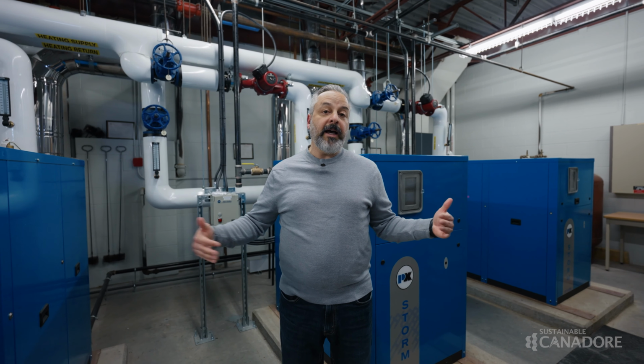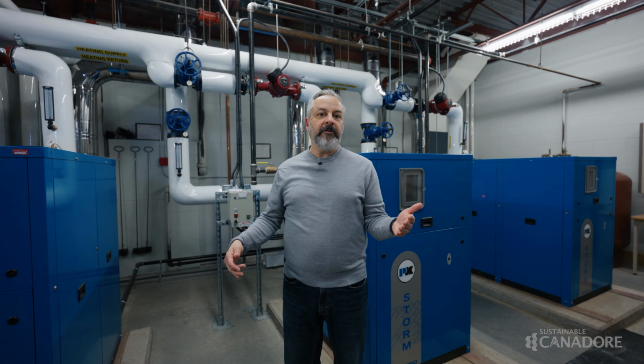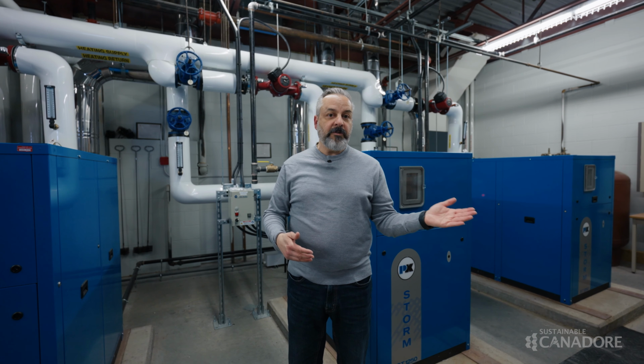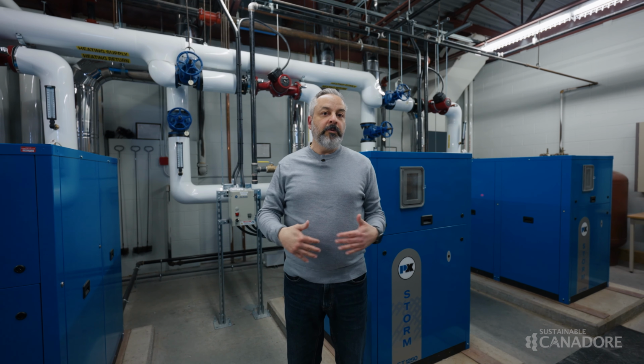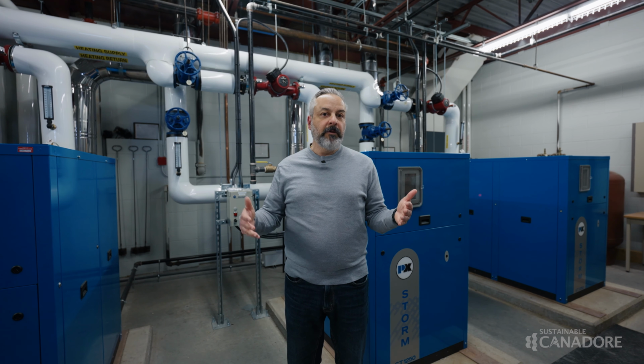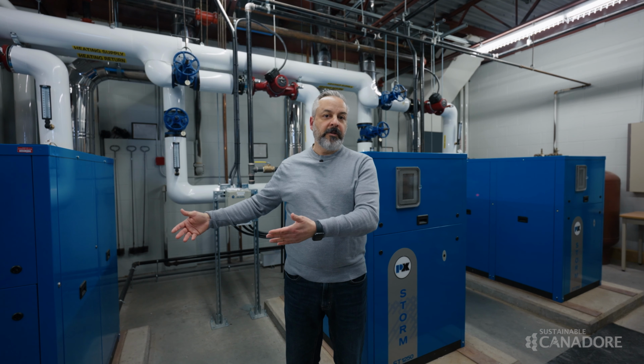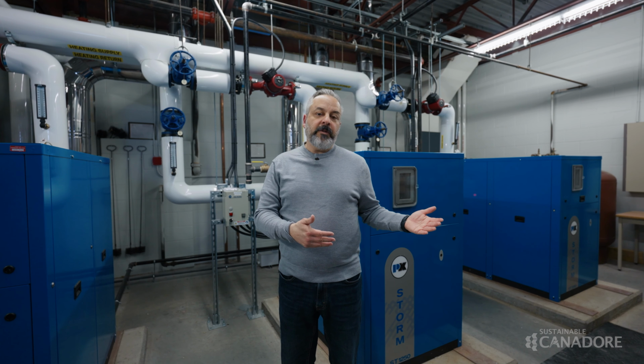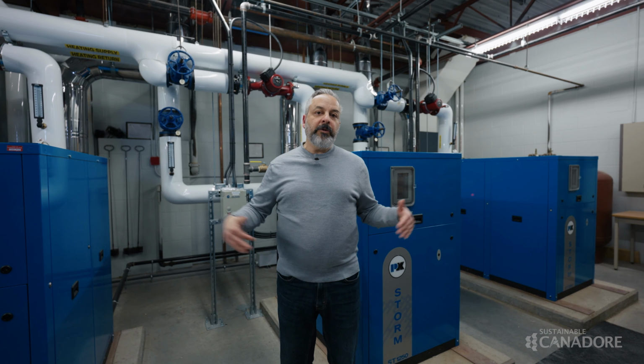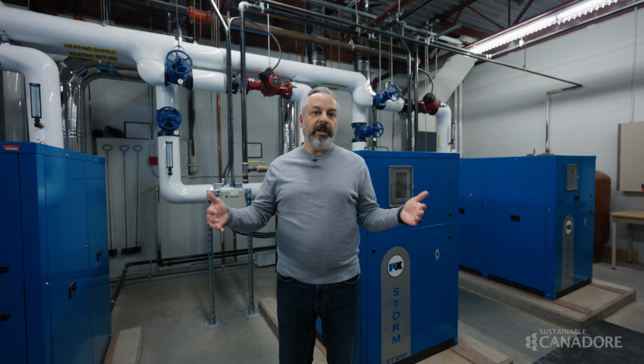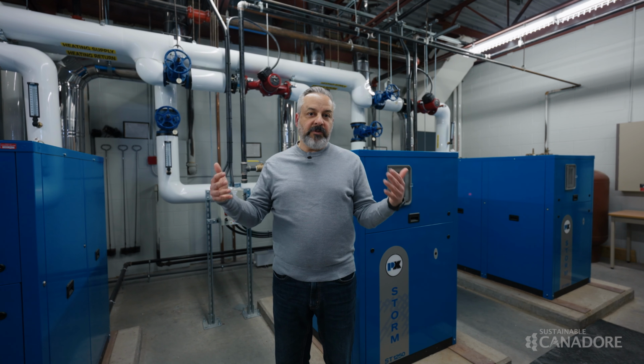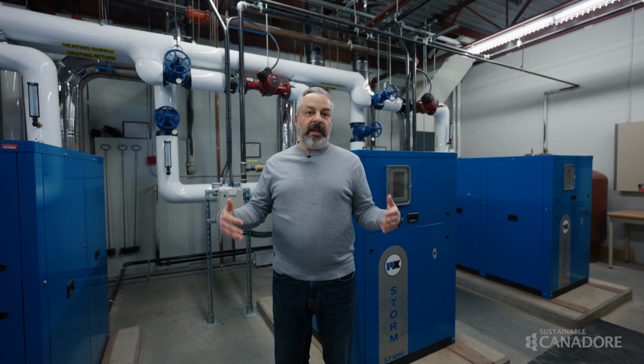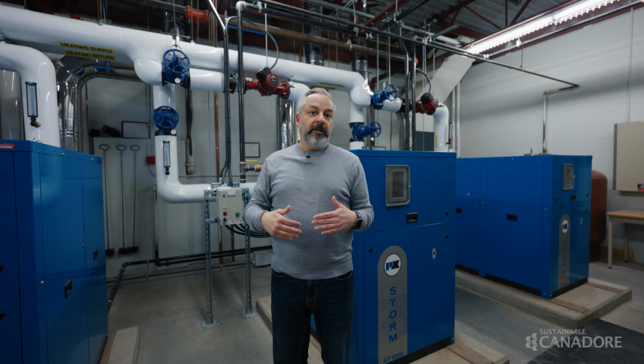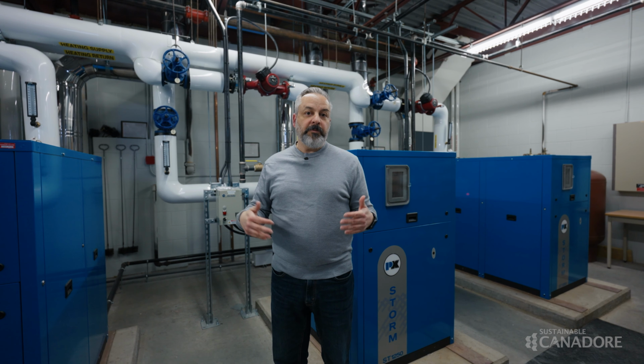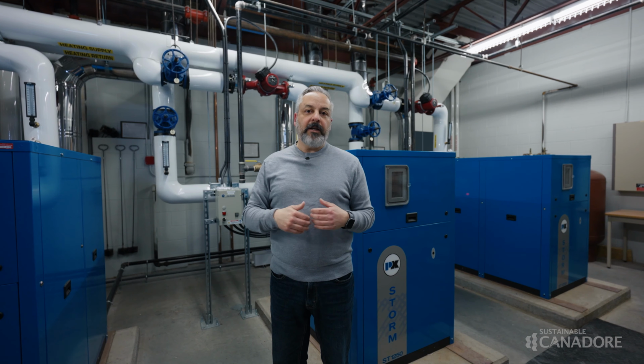So essentially we've gone from non-condensing boilers to condensing, high efficiency boilers, similar to the furnace you'd have in your home. If you go from a low efficiency to a high efficiency furnace, these new boilers capture all the heat they're producing and put it back into the campus. We've gone from an old system needing replacement to a brand new system that improved our efficiency by 25%, using 25% less energy to produce the same volume of heat for the whole campus.